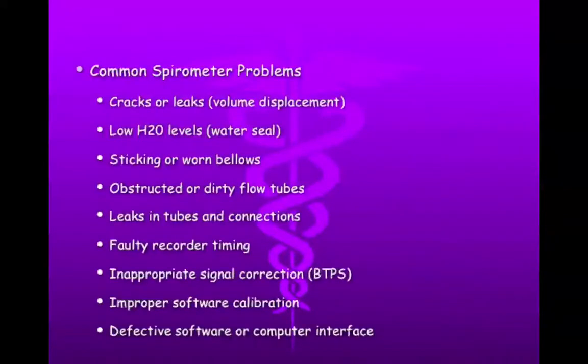Some real common spirometer problems that can cause some of our QC measures to fail are things like cracks or leaks within the volume displacement drums, low water levels if you have a water seal, worn bellows, obstructed or dirty flow tubes, leaks in tubes and connections. A faulty recorder timing can do it. Inappropriate signal corrections, your body temperature, pressure, saturated. Remember that when you're doing PFTs, we want to measure the volume in the body at body humidity and temperature. That's 37 degrees Celsius, 100% saturated. When you blow that air out into a room that's cooler, those values can change. So we have to be able to correct for those.